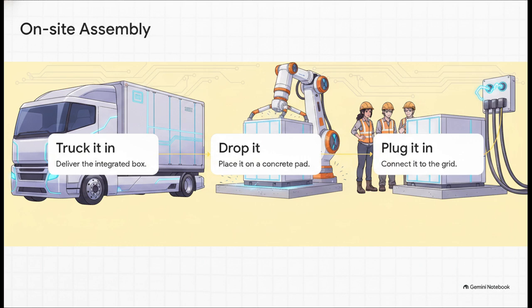These batteries are built at a mega factory in Lathrop, California, where literally everything—the battery modules, inverters, thermal management, the controls—is totally integrated into a single box before it even leaves the factory floor. So on-site assembly basically boils down to 3 quick steps: you truck it in, you drop it on a concrete pad, and you plug it in. It's practically plug and play on an industrial scale, which dramatically slashes assembly time.